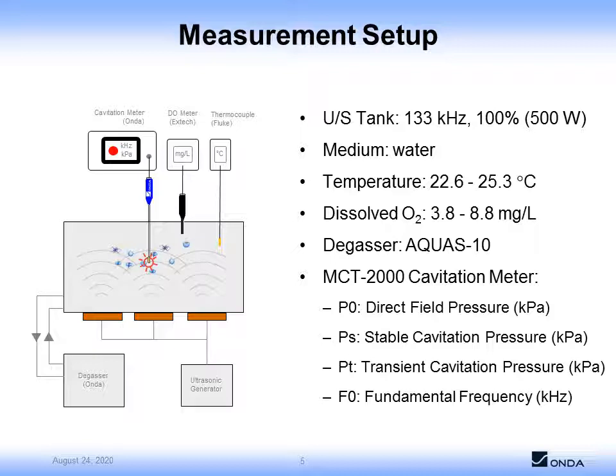The experiment relies on cavitation measurements in a 133 kilohertz ultrasonic cleaning tank that was coupled to an inline vacuum degasser. The medium is water, and the temperature is controlled within a range between 22.6 degrees Celsius and 25.3 degrees Celsius. To measure the dissolved gases, we use a dissolved oxygen meter as the degassing system varied the level between 8.8 milligrams per liter — which is the concentration of starting tap water — down to a degas level of 3.8 milligrams per liter. We used a cavitation meter called the MCT-2000 to measure the acoustic pressure from the stable cavitation, transient cavitation, and the direct field, as well as the fundamental frequency.